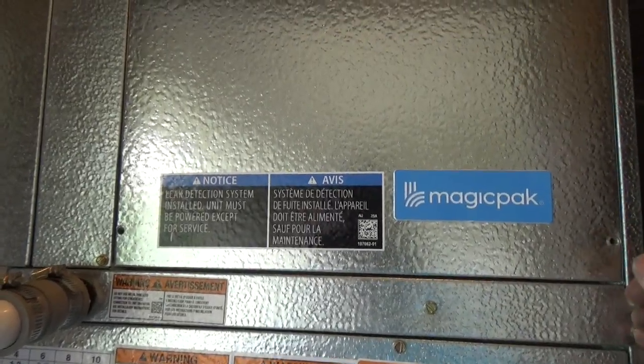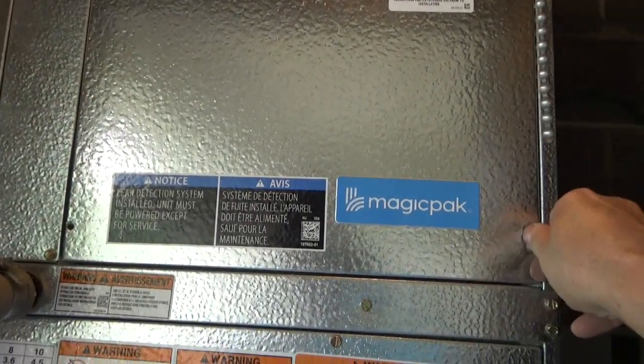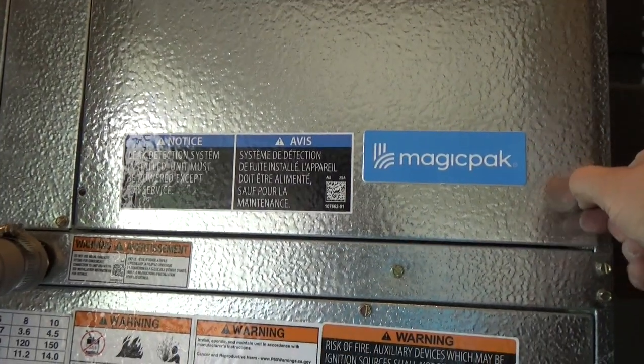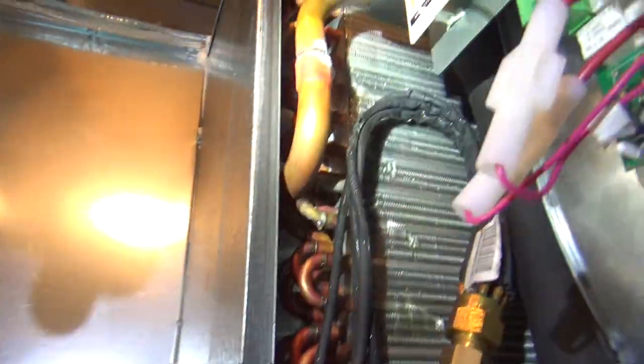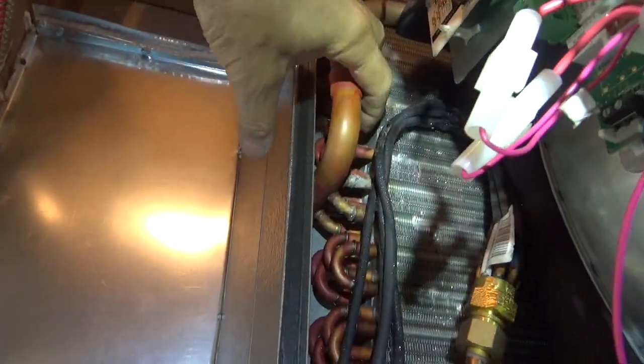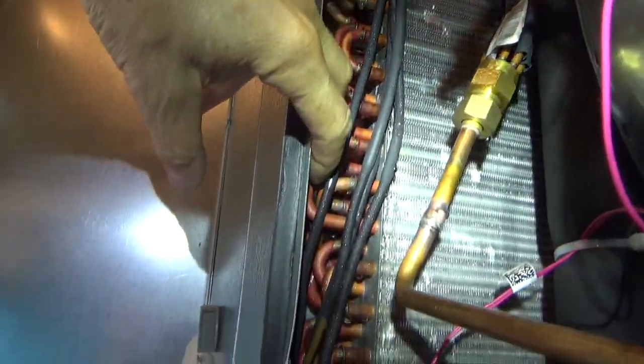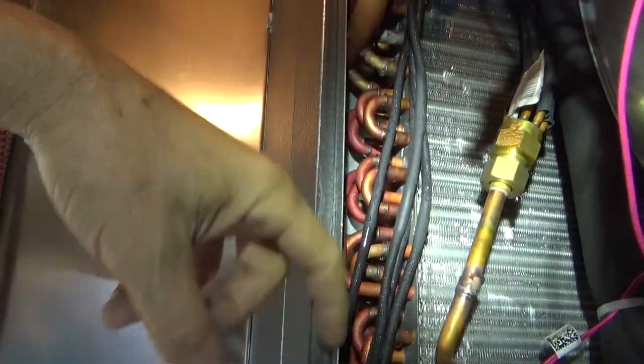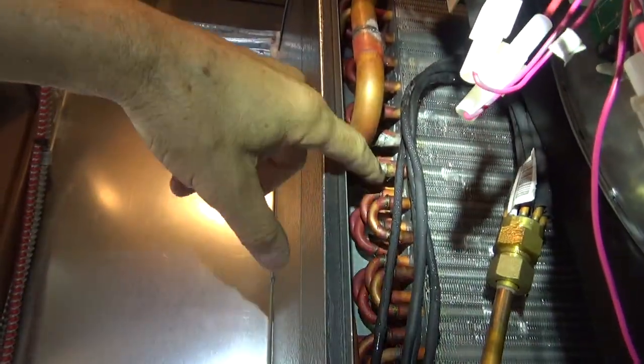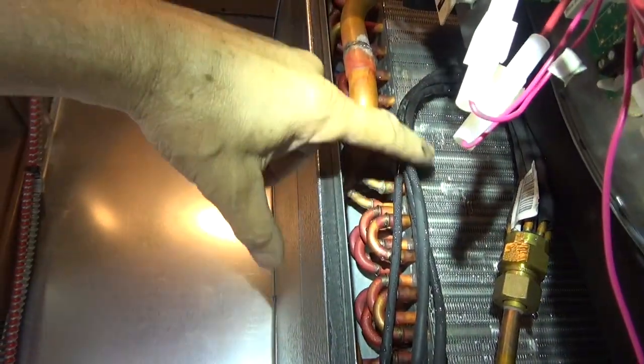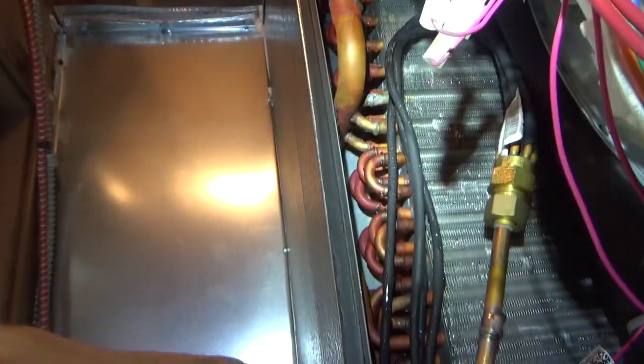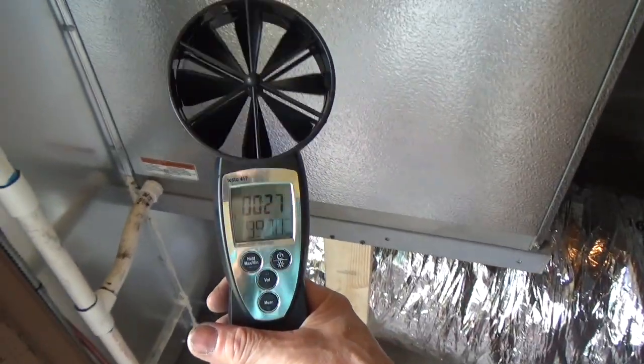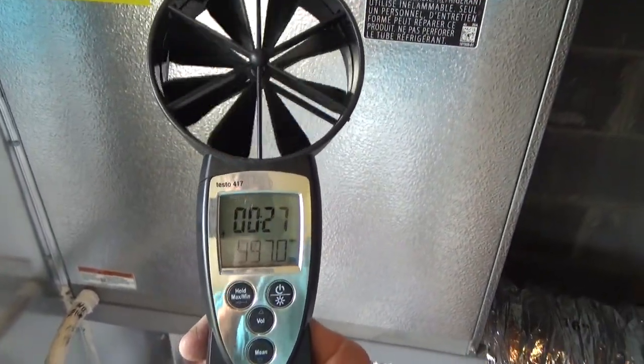While I'm bumping the fan speed up, let me show you how you check the Freon level on these units. What you do is you look on the evaporator. It needs to be 3/4 flooded. You can either use a thermal camera, or you can look at your sweat pattern. So we're sweating. This one feeds from the top and the bottom. The 2 tons just feed from the bottom, but we're dry just a little bit in the middle right here, and then we're wet everywhere else. So Freon level's good. So I actually had to go to the highest speed to get 1,000 CFM, 997.